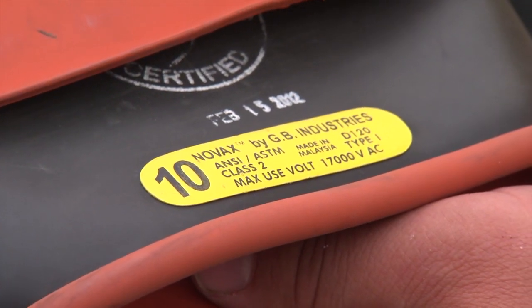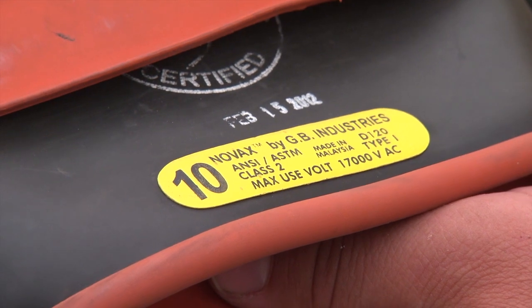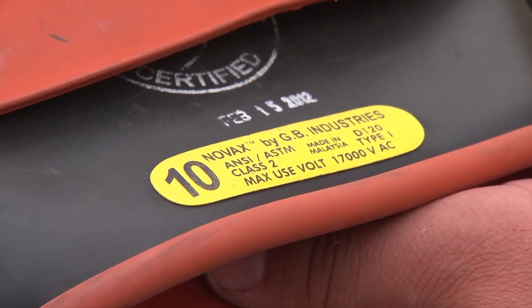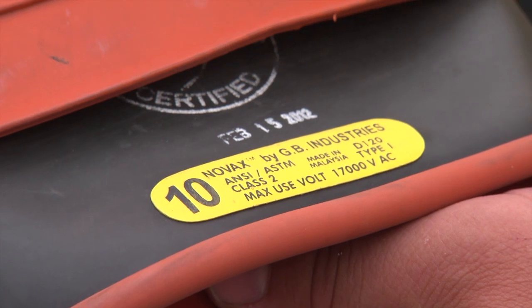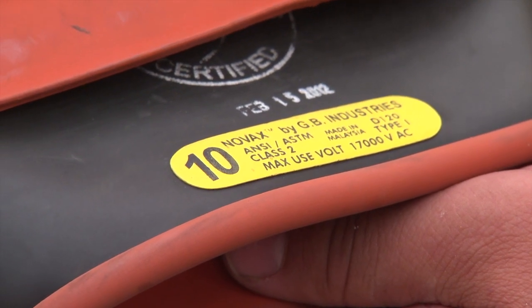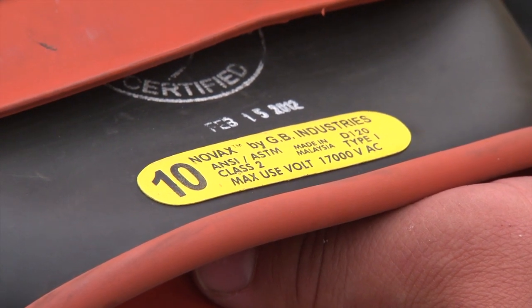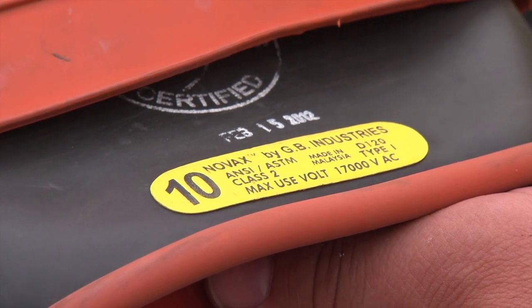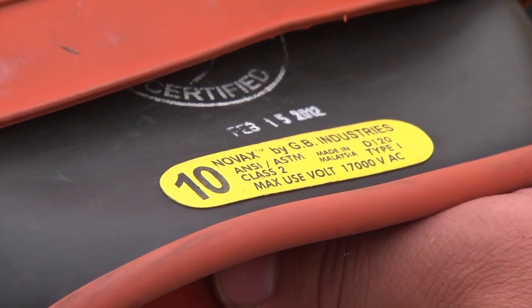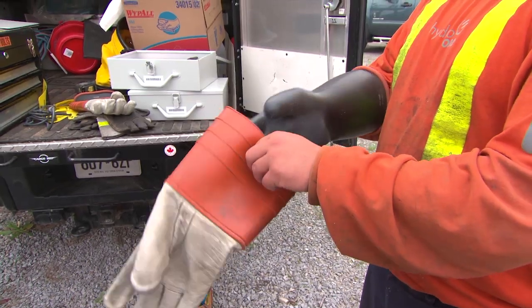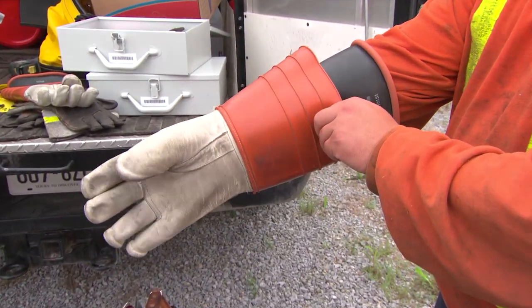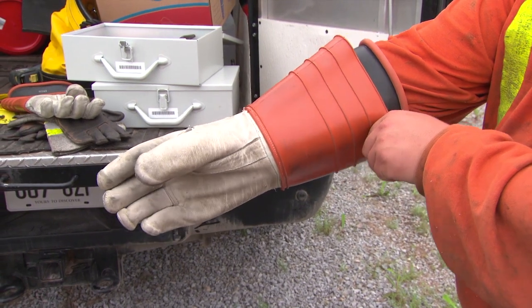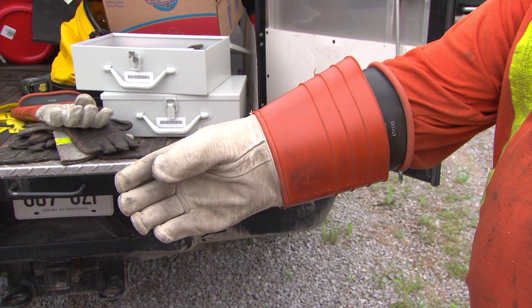Most rubber gloves are bicolored with a black rubber outer surface and either a yellow or red interior surface and cuff. The two-color fabrication of these gloves lets you easily identify points of wear or other defects in the outer black surface when the glove is inflated during inspection and air test. Rubber gloves are always worn with protective covers. These covers consist of a leather glove combined with a cuff of synthetic or leather material. This cuff is for mechanical protection only and is not to be relied on for electrical protection.